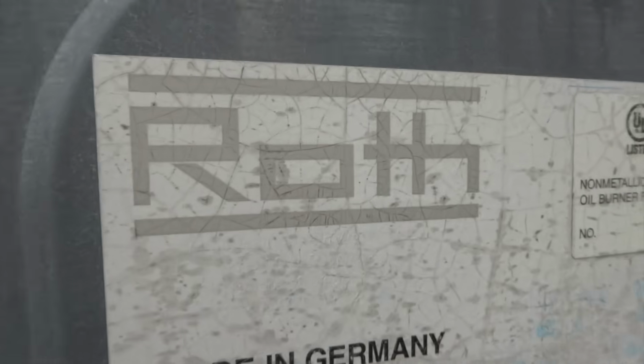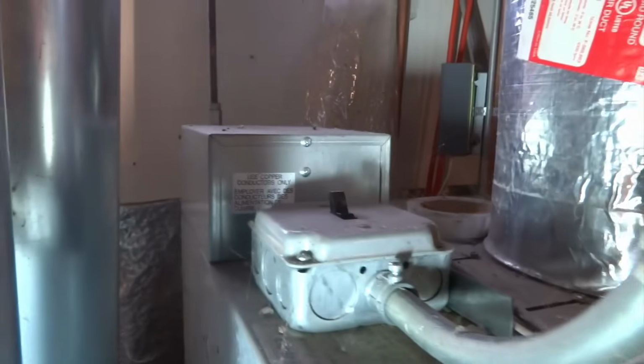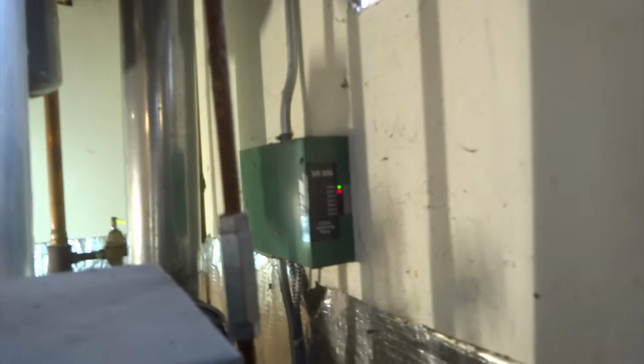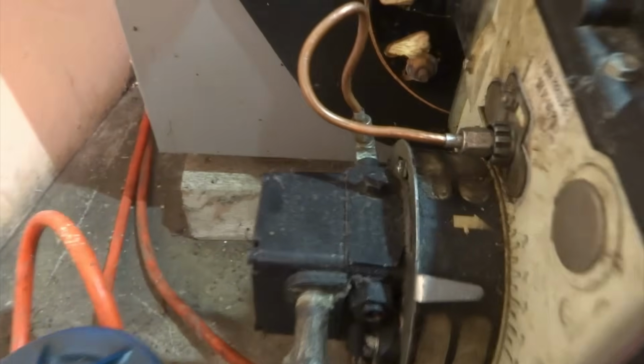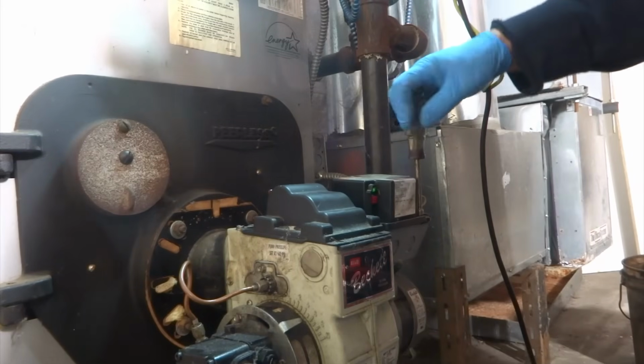Made in Germany. All right, so he said he's got it off here and he's got it off at the air handler. So I should be calling if I turn this on. Yeah, we got one zone calling. Plus, this thing maintains temperature, I believe. So it should be off on. Yeah, it's off on. Like that, see all that wire is? We'll fix that. Could be this transformer's bad. That's what I'm thinking. No delayed oil valve. We'll fix that wire first thing.